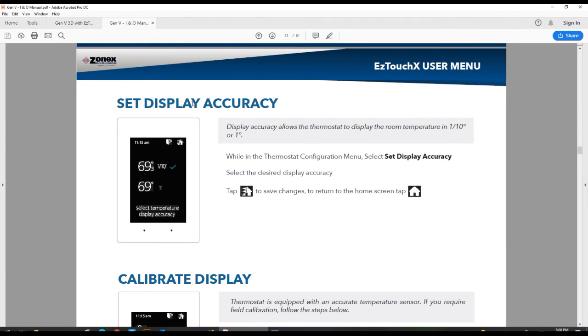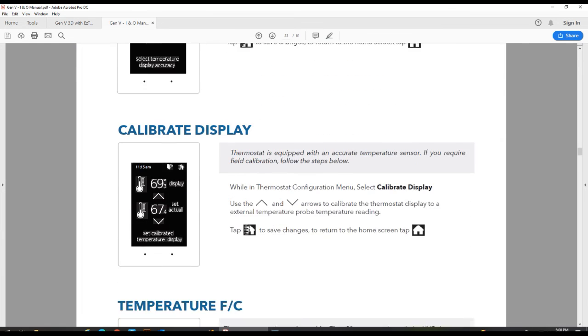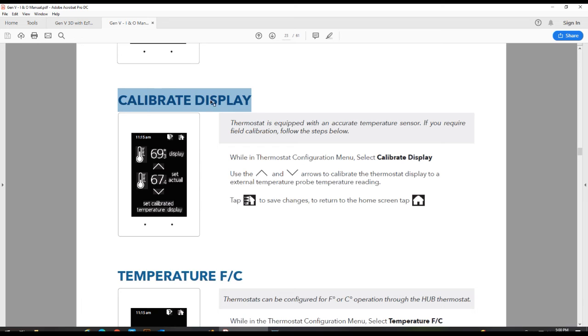All right, display accuracy. We offer two display accuracies. One is a full degree, so in this case 69 degrees. The other one is we show the tenths of degrees, so 69.3. So if you'd like to show the tenths of degrees, go ahead and select that, and that will show up on your main display. For whatever reason you feel the need to calibrate the thermostat or display, if it seems a little out of range, you can go ahead and calibrate it and bring it closer to the expected range it should be.